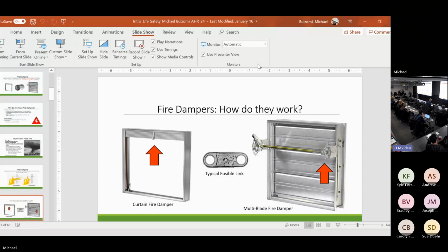This is just going to be a function of a manufacturer's UL listing. So I do my test. I get a listing of a 100 by 100 for a curtain damper. I know I'm going to need something bigger, and I could pass 200 by 200 with this. So every damper in my submittal up to 100 by 100 is going to be a curtain damper, and then everything over that's going to be a multi-blade fire damper. Well, maybe my competitor was a little better in their testing, and they could do 150 by 150. So all their dampers up to 150 are going to be curtain style.